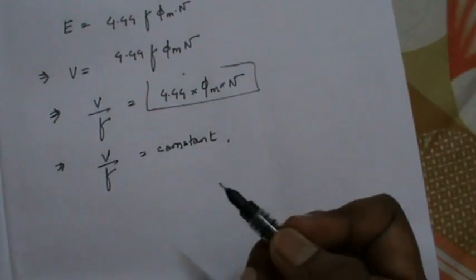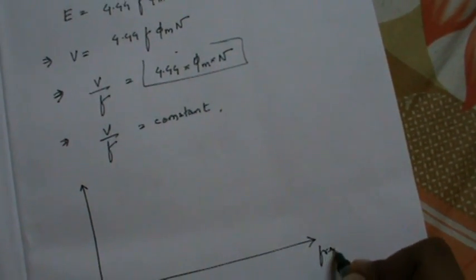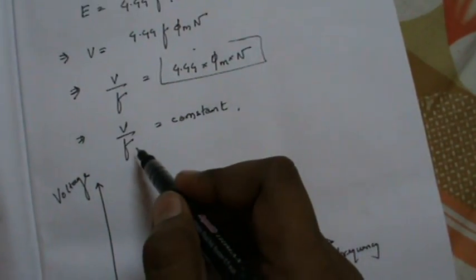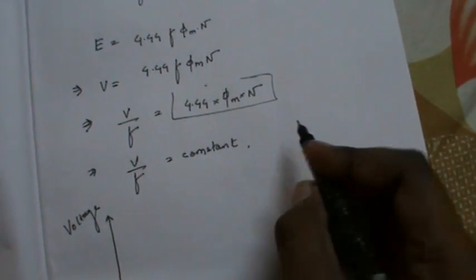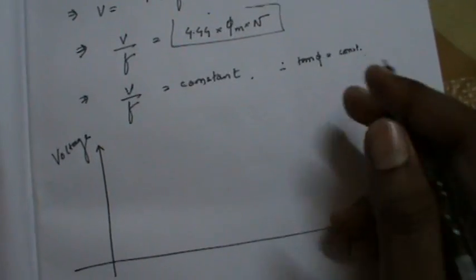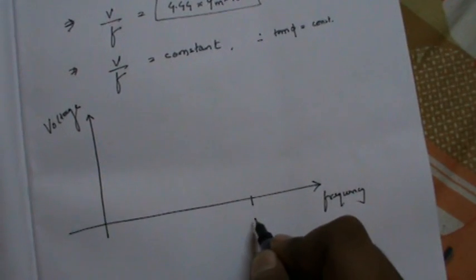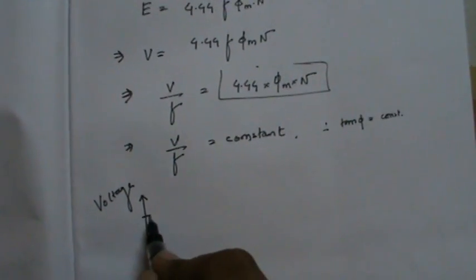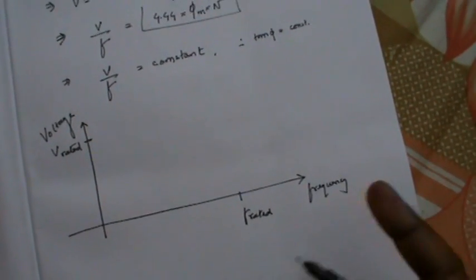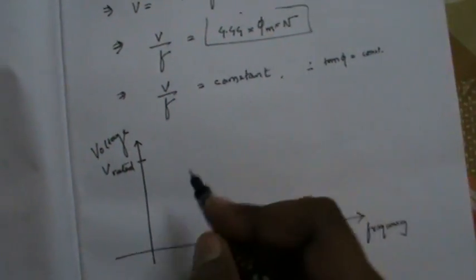Now let us concentrate on the practical significance of this. We will draw a graph with frequency on the horizontal axis and voltage on the vertical axis. V by F is actually a slope, and when this slope is constant it means tan theta is constant. The rated frequency is 50 Hz and the rated voltage for a three-phase system is typically 400 V. We draw this graph according to our system parameters.